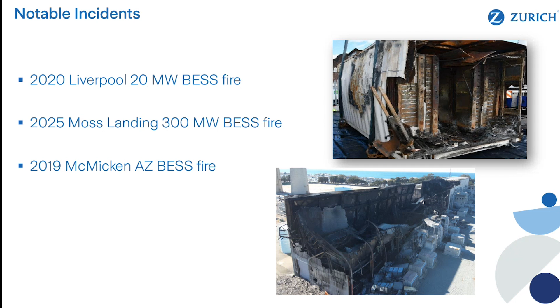The good news is the new technology we're using, lithium iron phosphate, is a lot less susceptible to thermal runaway. It releases less oxygen, it doesn't want to go into thermal runaway - it needs to be pushed very hard to even go into that state. So with the lessons learned from some of these incidents, and following the guidelines, i.e. the separation, using detectors, etc., these problems should be avoided in the future.